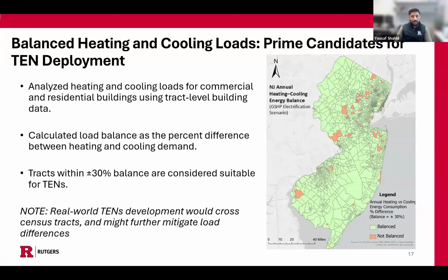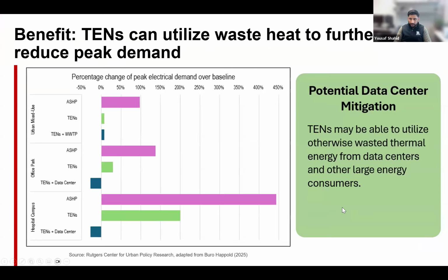Can we go back to the previous slide? Yes. So just to add on, the waste heat offsets part of the thermal load, so the heat pumps don't have to work as hard. That's a primary reason for the reduction in peak. That directly lowers electrical demand.